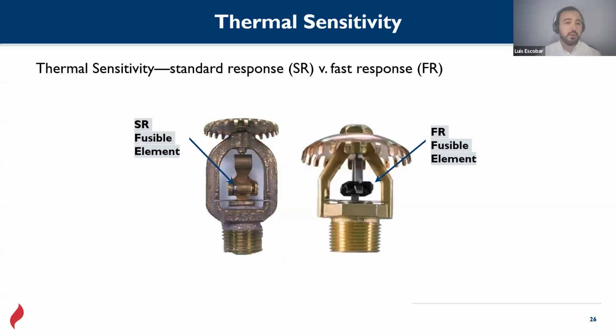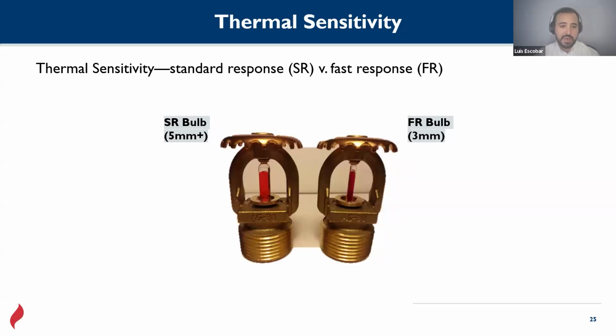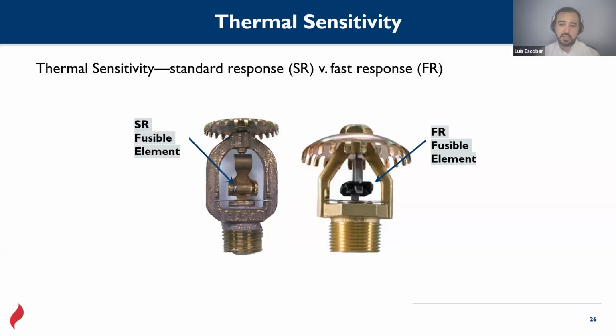Sorry, let me go to the next one. Here you go. All right. There's another type of sprinkler that has another type of activation: the fusible element. This part that you see here on the sprinkler is called the fusible element, and it has the same function as the bulb. When this one breaks, the water is released, and when this one moves, the water is released. This one follows the same principle as the previous one. When the heat starts expanding this metal, it moves and lets the water start flowing through. Okay. What will be the main difference between bulb sprinklers and fusible element sprinklers?